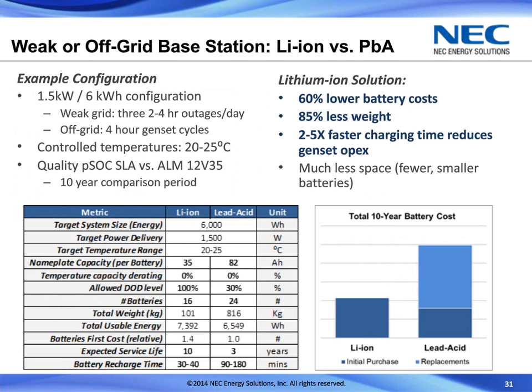So for this example, 1.5 kilowatt, 6 kilowatt hour. So that gives us a 4-hour runtime. We're controlling the temperature, so between 20 and 25 degrees C. Comparing a quality partial state of charge optimized SLA battery versus our ALM 12V35, again over a 10-year period. So I won't spend as much time on these numbers, but 35 amp hour lithium battery again, and now compared to an 82 amp hour lead acid battery. So it's a bigger battery, but due to the allowed depth of discharge, you still need more of them.